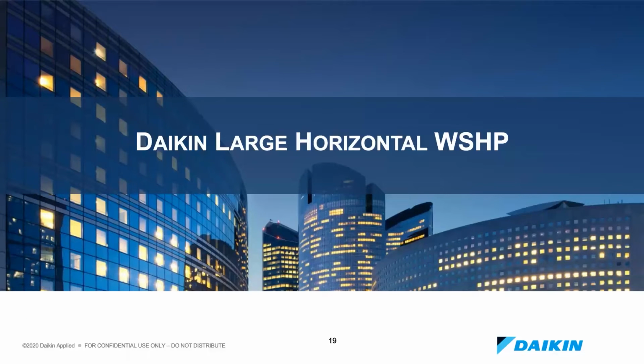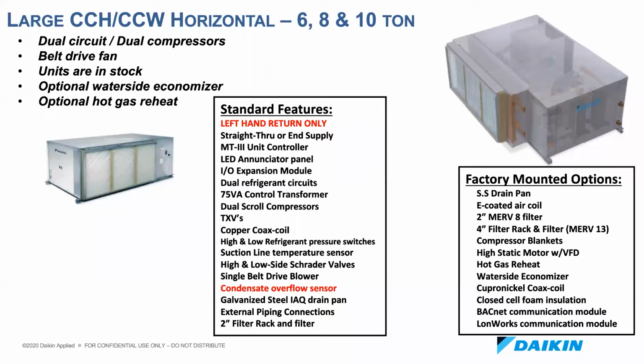Next is our large capacity horizontal products, also part of the Enfinity lineup, which share the same model names as the smaller sizes, WCCH and WCCW. It's available in a 6, 8, and 10 ton capacity model, available in left-hand return only. It has dual refrigerant circuits, dual compressors, and a belt drive fan system. Some of the popular options for this model are the water side economizer and hot gas reheat.